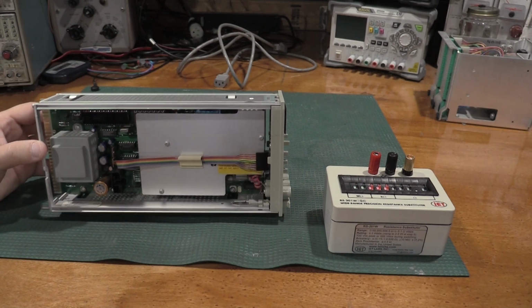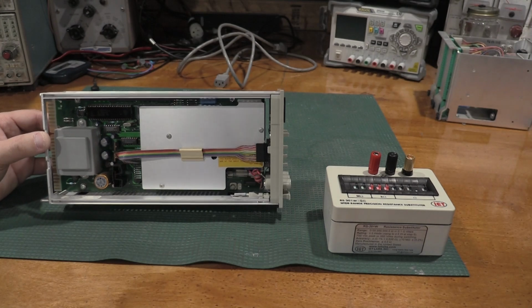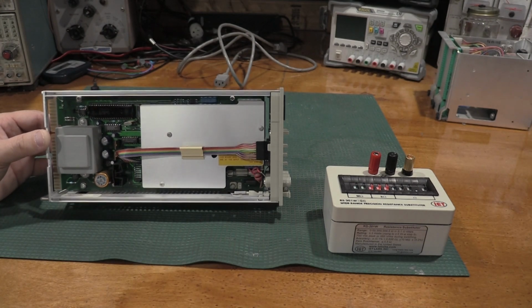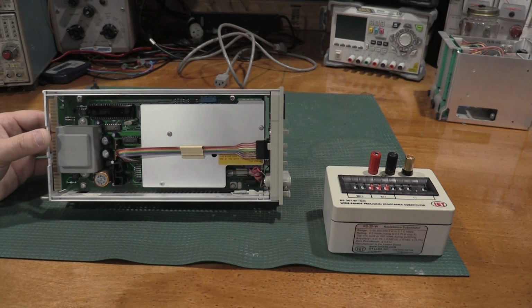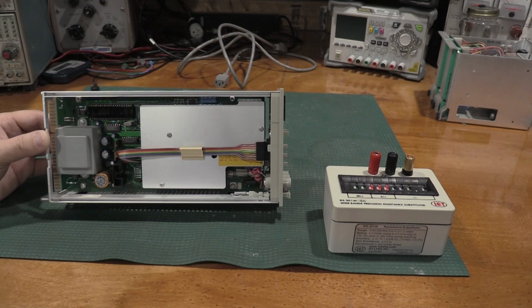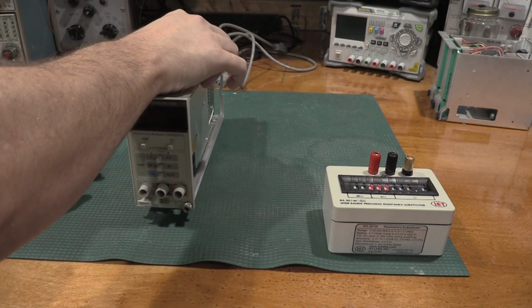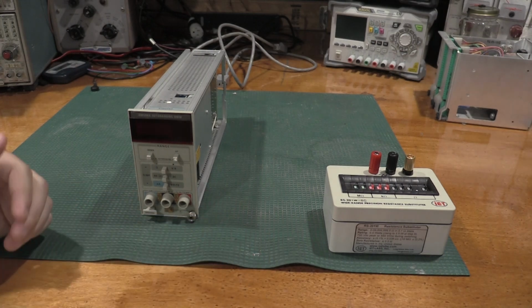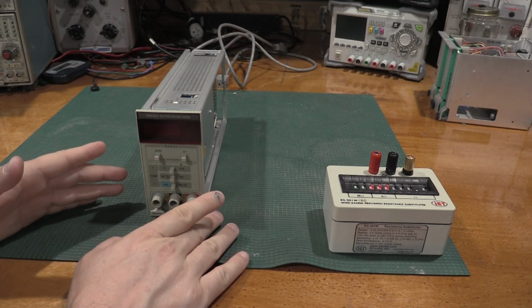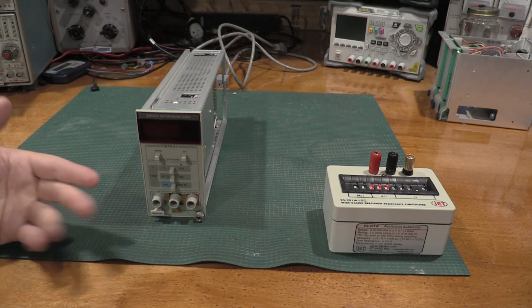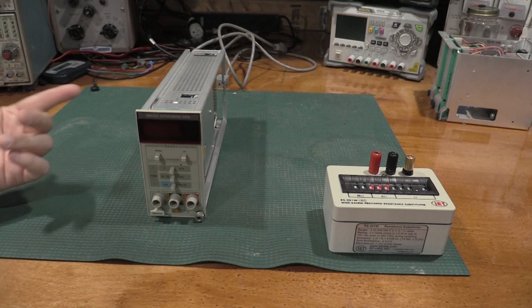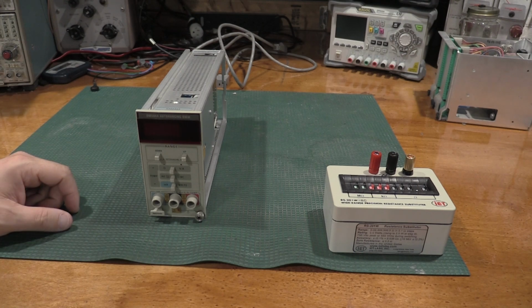So the alignment steps on this particular meter, it's not complicated. Once you have all the sources, it's not complicated. Getting some of the sources can be quite complicated. But it's incredibly time-consuming, because there's, I think, 50-ish alignment points that need to be done up through the meter. And basically what the meter's doing with the alignment is, when you calibrate the meter, you're putting in a known source, and you're telling the microprocessor, this is what it is. It's storing an offset, and that's how it makes measurements.